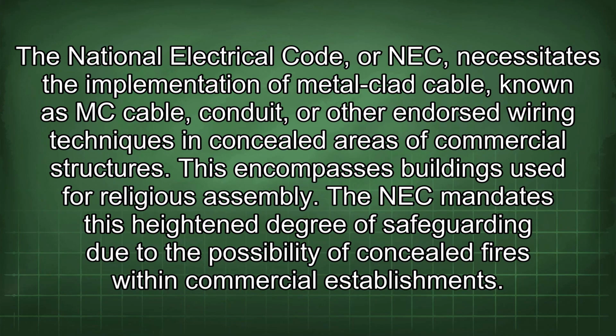The National Electrical Code, or NEC, requires the use of metal-clad cable, known as MC cable, conduit, or other approved wiring methods in concealed areas of commercial structures. This includes buildings used for religious assembly. The NEC mandates this heightened degree of protection due to the possibility of concealed fires within commercial establishments.